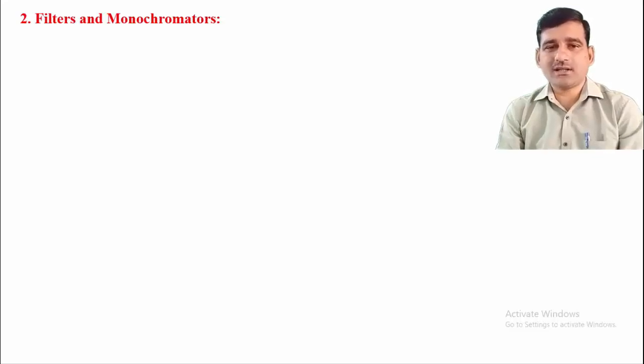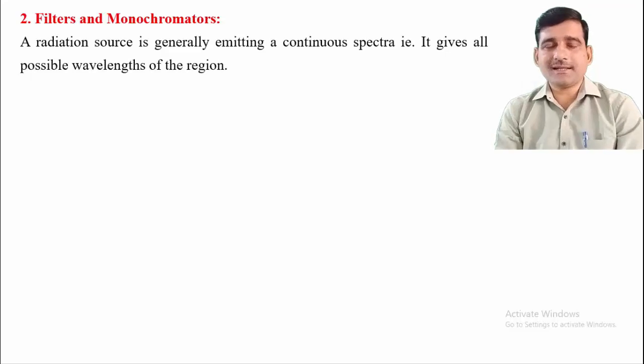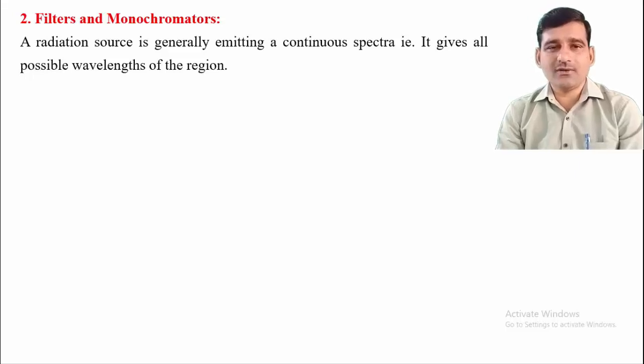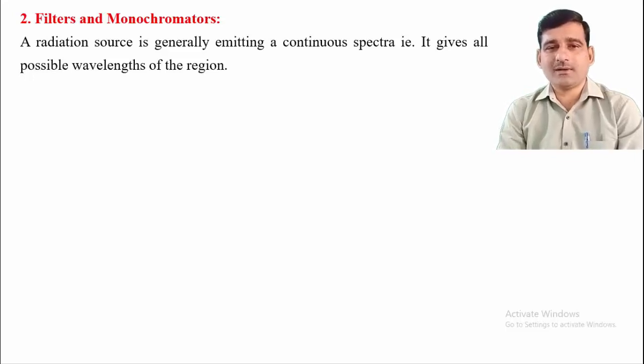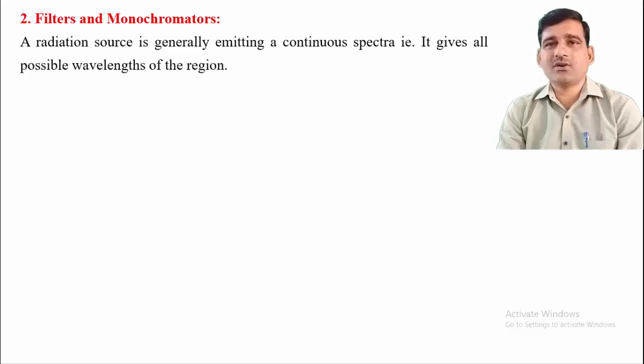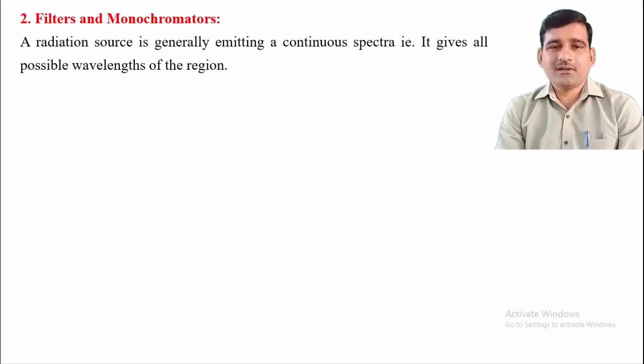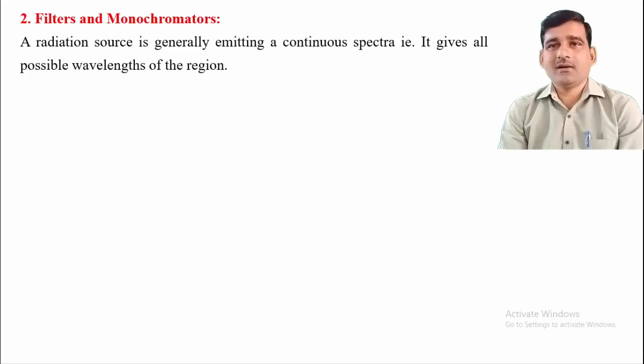Filters and monochromators are two different terms. Filters are devices which can transmit only a desired wavelength of light — they filter the light. A filter absorbs all other radiation and transmits only a particular band of light, giving a bandwidth of around 25 nanometers. A radiation source generally emits a continuous spectrum from 400 to 800 nanometers in the visible region, and from that range we require a particular wavelength, for which we need filters or monochromators.